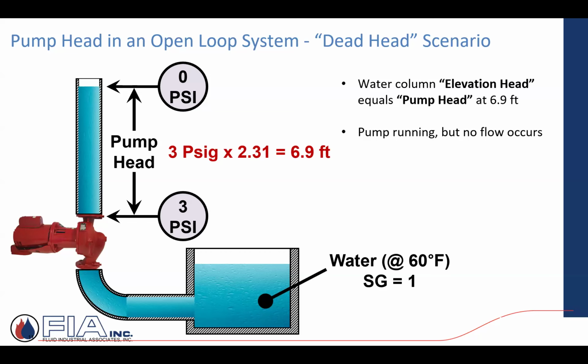It's an interesting screenshot or drawing here, but what it's showing is a pump operating in an open loop system. And they'll use the expression dead head up at the top here. So what they're saying is, based on the height of this open pipe, I have this circulator or pump, its suction is flooded, and it's pulling from this basin or container of water. And what it's saying here is the water column, or the elevation head, equals the pump head, which is a 3 psi differential, or 3 times that 2.31, which equals 6.9 feet of head. So in this weird, unusual scenario, I could turn the pump on and the pump's running. It's developing 6.9 feet of head and no water's flowing.